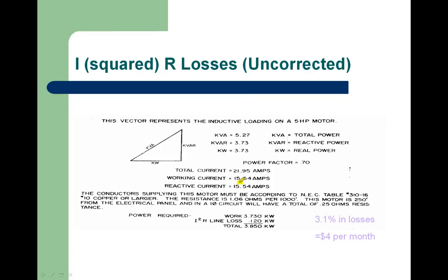So if you squared these two values here and took the square root of that, you would end up with 21.95 amps. So in this particular case, we have a motor which would be drawing 3.73 kilowatts right here. That would be if the motor was right next to the hydrometer. Now, if we took that motor and moved it, I think it was actually 250 feet away. I think this says 1,000, but I don't think that was the case. It's about 250 feet away.